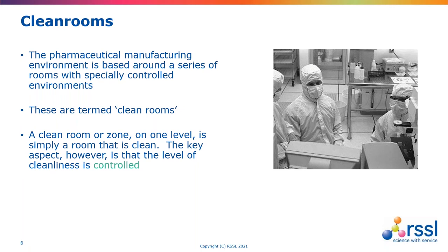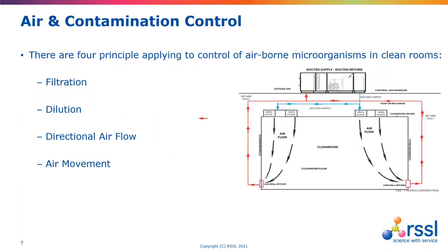If we consider the outside environment, typically the air contains around 35 million particles per cubic metre. In a grade B clean room, we're seeking particulate levels hundreds of thousands of times less than that. So we need to exclude those particles from entering the clean room, ensure particles generated within the room don't settle in critical places, and drive those particles out of the room fairly rapidly. We achieve that through four key principles: filtration, dilution, direction, and air movement.